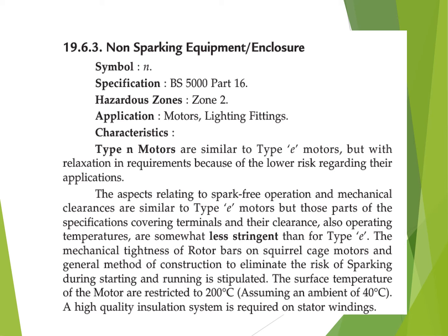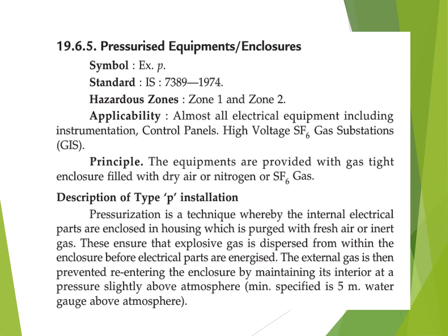So here we can use this application. It is mainly used in motors and lighting fittings, and it can be used in zone 2. For motors, the aspects of spark-free operation and mechanical clearance are similar to type E motors, but here the mechanical tightness of rotor bars of squirrel cage motors and the general method of construction to eliminate the risk of sparking during starting and running are stipulated. A high quality insulation system is required in this.